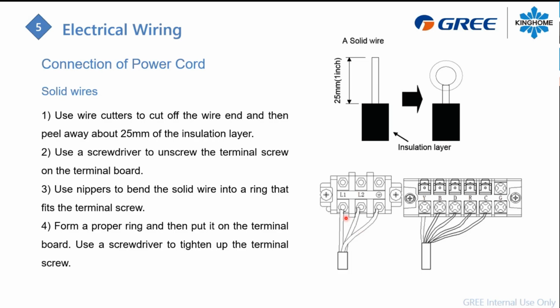So when you do your connection, it's good to have a good and solid connection on your L1, L2. If you use some spade connection, that's better. If you just lay your solid wire like this, make sure you have long enough of that copper wire here to make a good connection for your L1, L2, and your ground as well. For the low voltage connection, it's highly recommended to use stranded wire. But if you have some solid wire, because it's only a 24 volt connection, again, make sure you make a good contact here with the copper to avoid any electrical problem with the system.